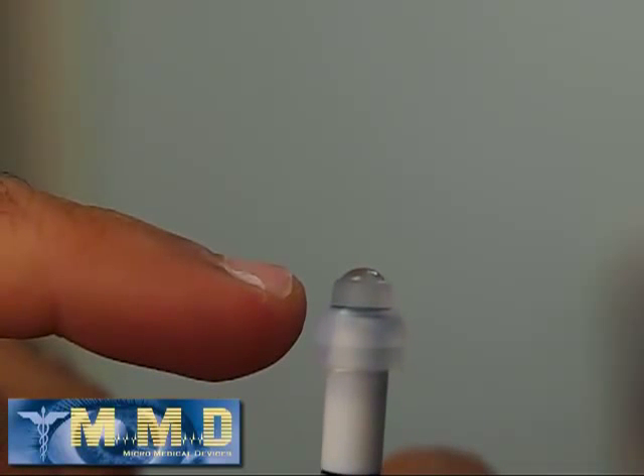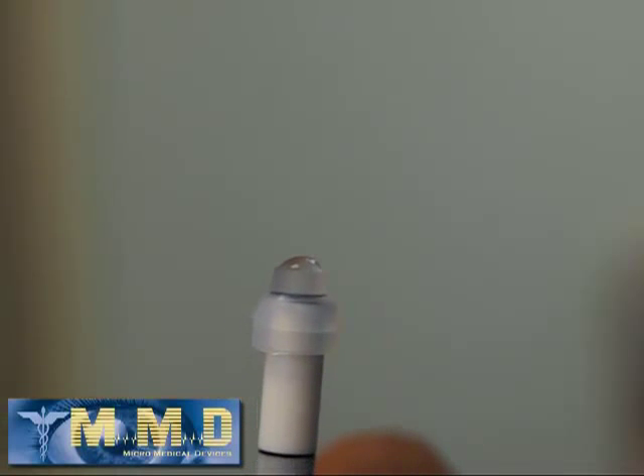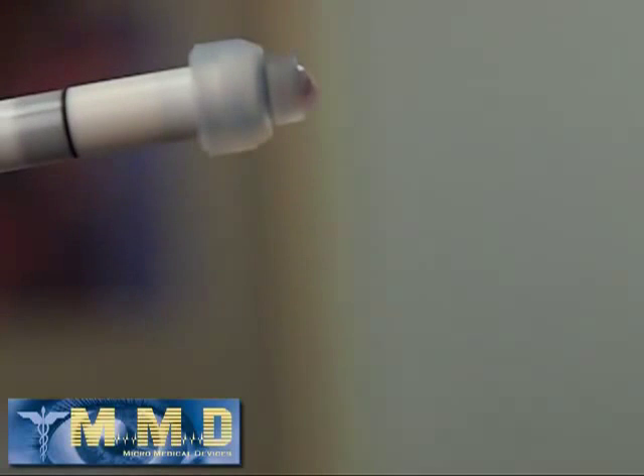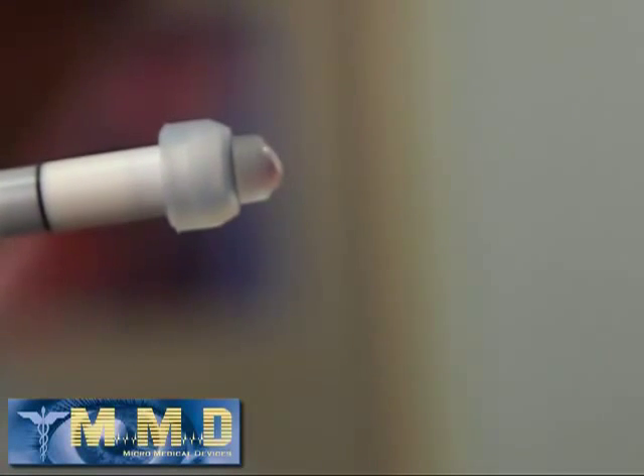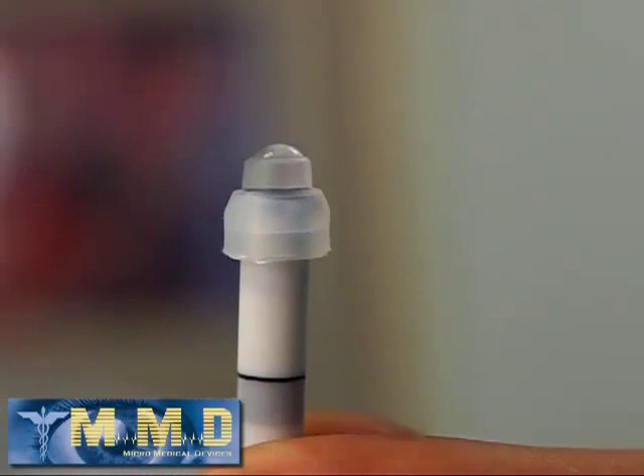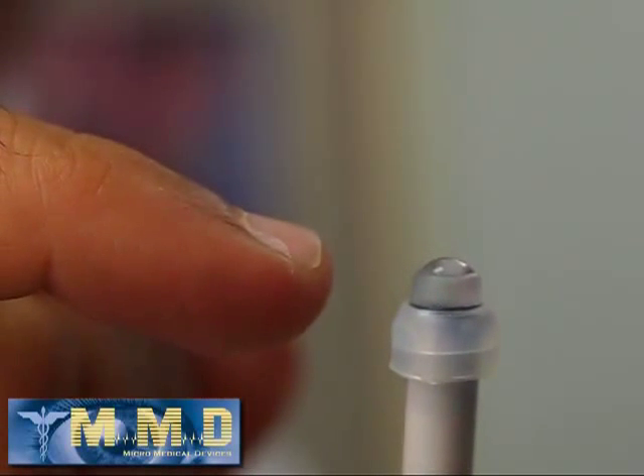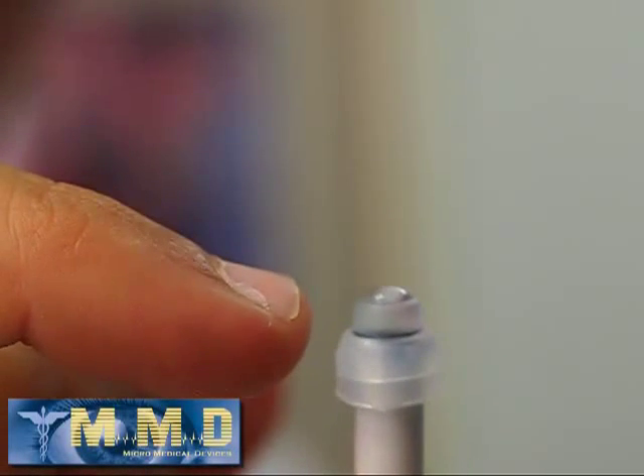I'd like to re-emphasize the proper amount of meniscus on the easy immersion tip. As you can see, the proper amount is just enough to have about a 1 millimeter or 1.5 millimeter dome. You don't want to overflow the dome, because when you hold it in a horizontal position, if you have a dome that is too big, the dome will cause a prismatic effect on the LED light, and the patient might not be looking directly at the LED. So, as I said, this is just about the perfect amount of dome, and just bear in mind that when you do this exam, if you do it right, you only transfer this amount of fluid to the eye, and you keep the rest of it in the chamber. And all you have to do is introduce half the amount of drop back on the dome to do the other eye.